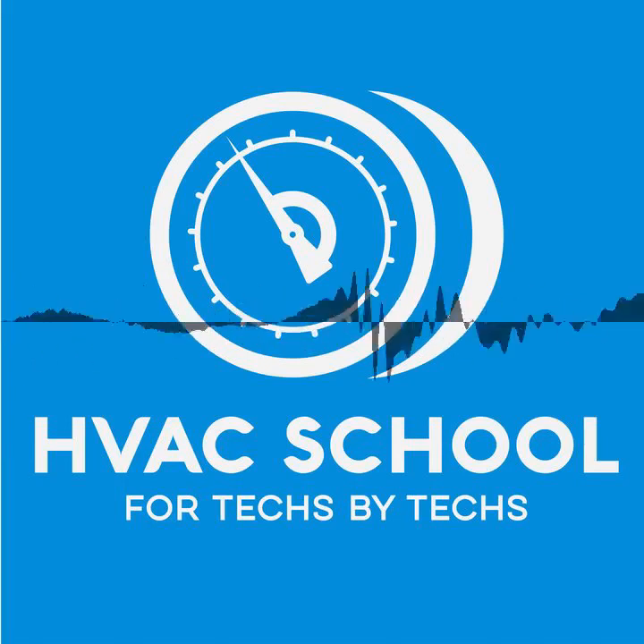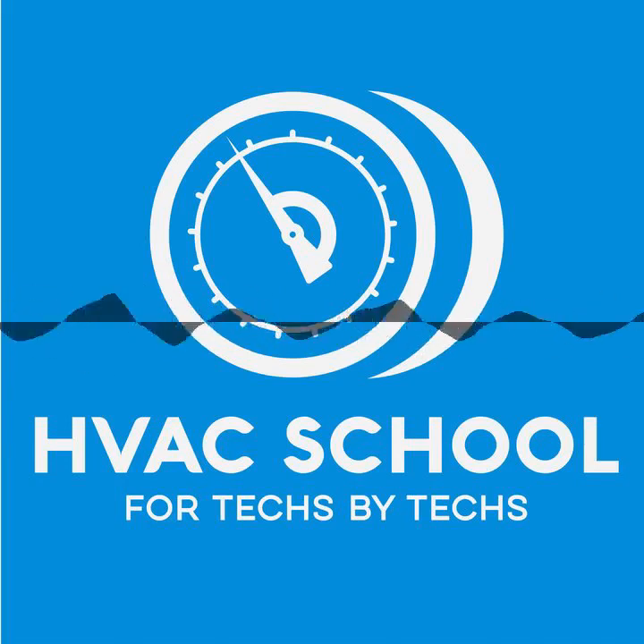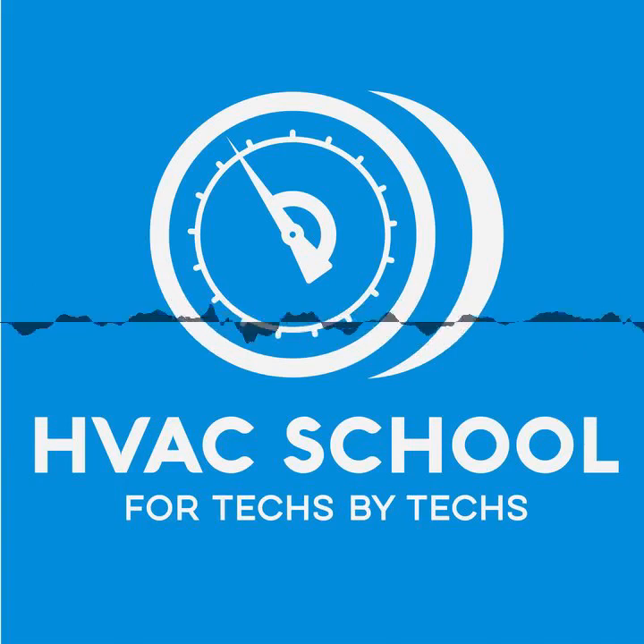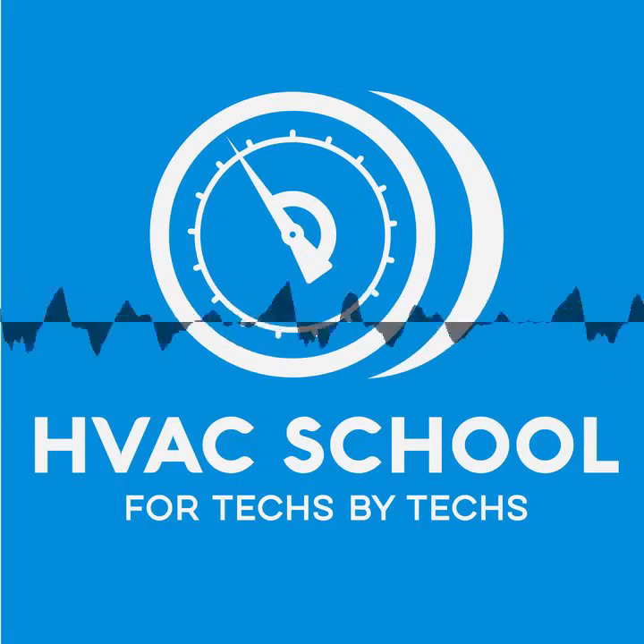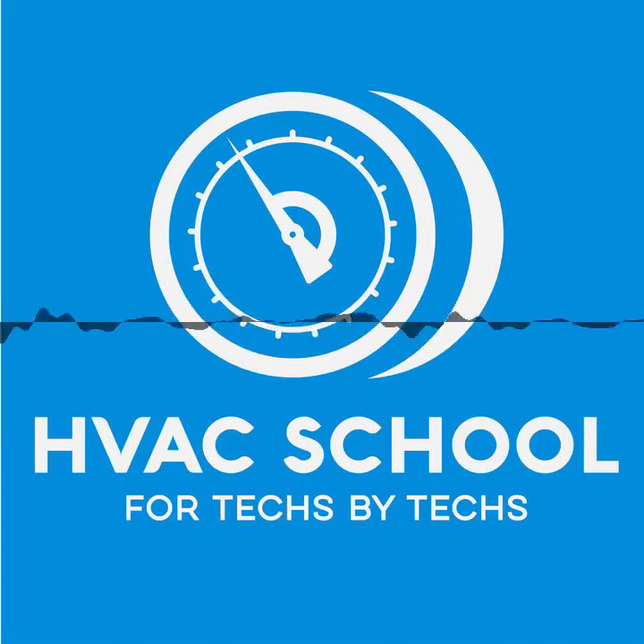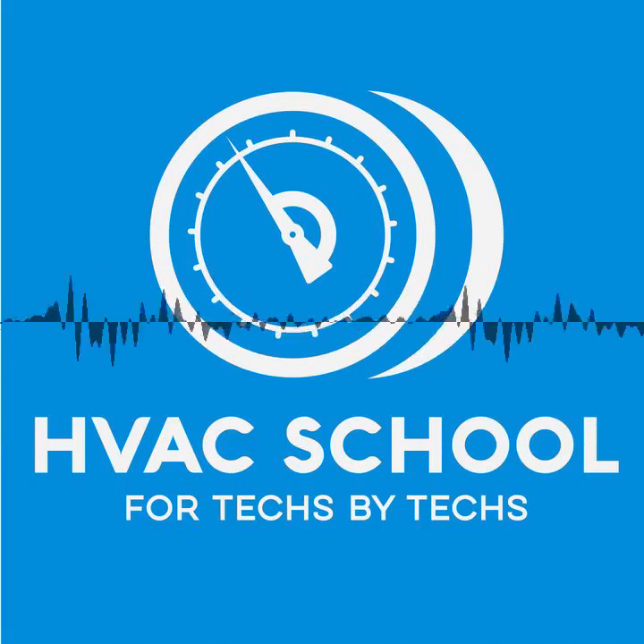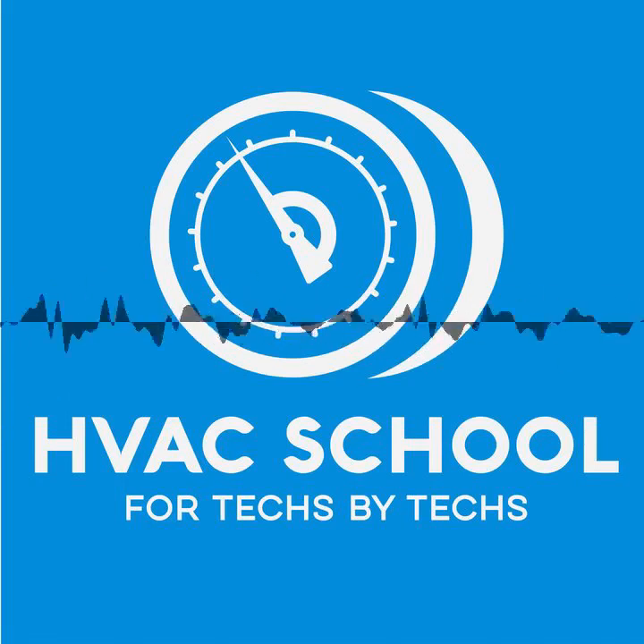load. And one of the things you've got to think about with electrical is there's two characteristics that are really important. One is electrical pressure, which is your voltage, and then electrical flow, which is your current. And you can have very high pressure or normal pressure, but not have good flow. And what I'm talking about in this case is, let's say that you have a conductor that somebody couldn't quite get underneath the contactor, so they trim back a few leads on there, right, to make it squeeze underneath the terminal. We've all seen guys do that, right?